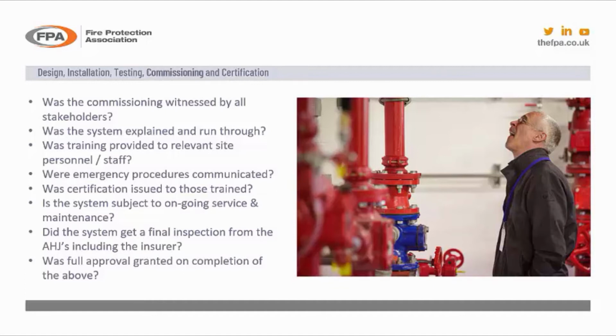Another thing that's critical to the certification of the system is you must have an ongoing service and maintenance agreement with a third-party approved contractor. So not only have they demonstrated the system, they've provided you with service and maintenance for maybe the first 12 months of the system. Did the insurers or the AHJs do a final inspection of the system and sign it off? You will have had, hopefully, if you followed the process through correctly, written approval on the drawings based on site inspections, subject to final inspection maybe. Did the insurer do the final inspection? Has it been signed off?